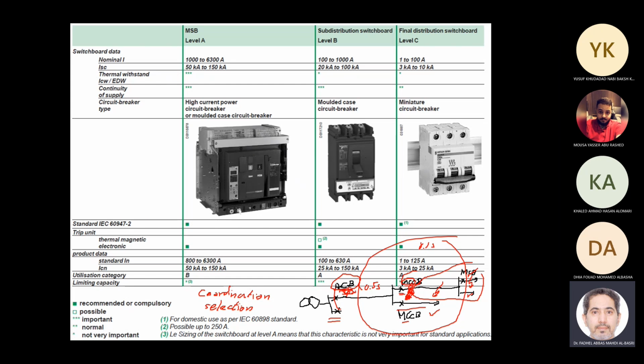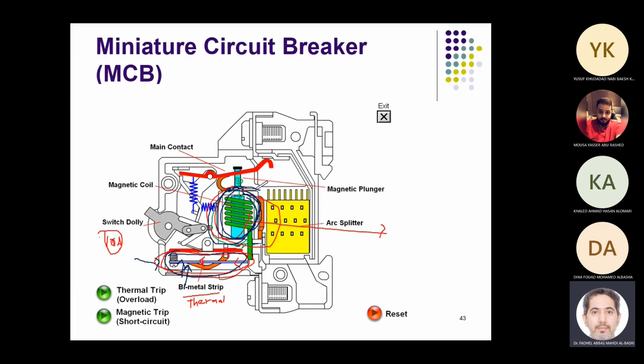Meaning the breaker's ability to extinguish the spark that results after the breaker opens the circuit, or during the opening of the contacts of the breaker. An arc is initiated, and this needs to be cleared or quenched quickly by the mechanism. There is a method that makes a breaker able to break higher breaking capacity. Inshallah, the principles of those arc quenching mechanisms will be presented today.